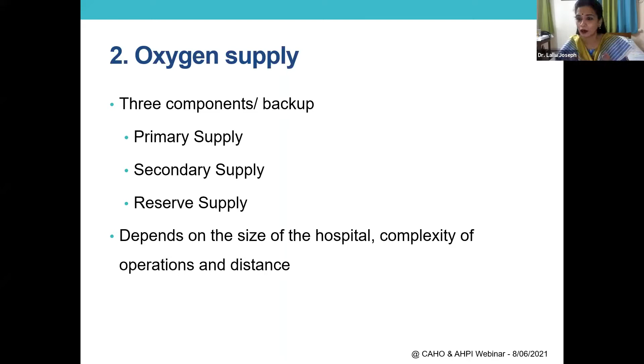Please understand, if your primary supply is a gas cylinder manifold, you're a 100-bedded hospital and you're using a manifold, then the primary supply should have auto changeover, which means if your left bank is running out, it has to automatically change over to your right bank.